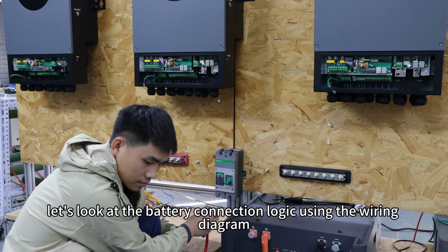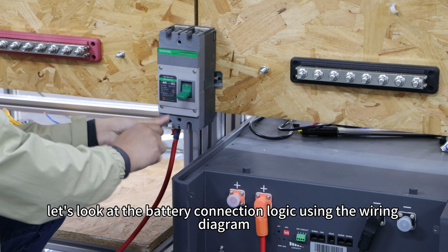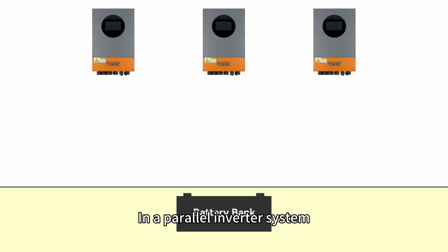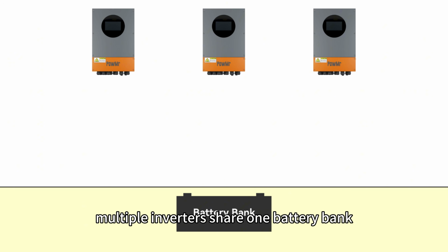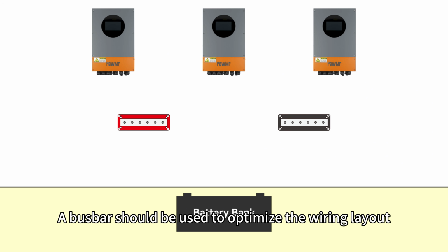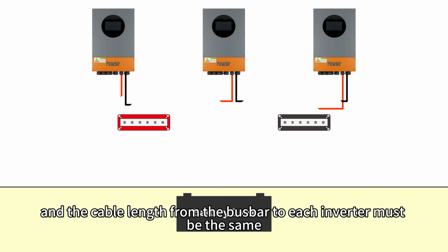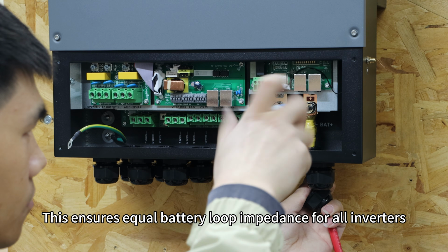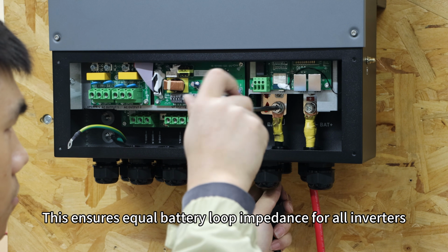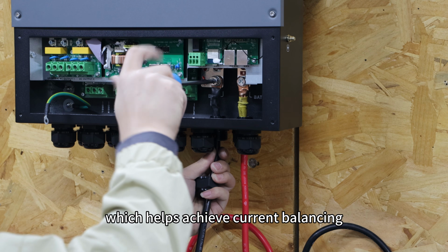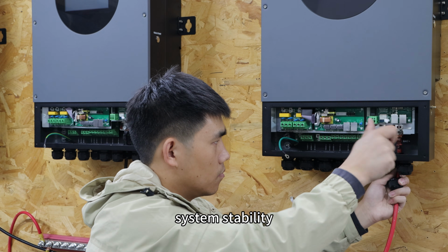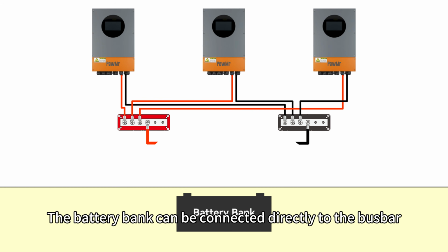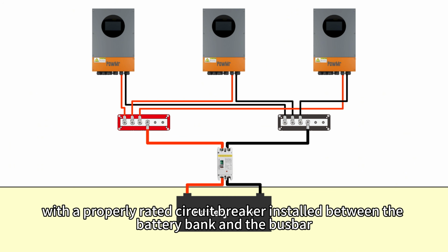First, let's look at the battery connection logic using the wiring diagram. In a parallel inverter system, multiple inverters share one battery bank. A bus bar should be used to optimize the wiring layout, and the cable lengths from the bus bar to each inverter must be the same. This ensures equal battery loop impedance for all inverters, which helps achieve current balancing, system stability, and equipment safety. The battery bank can be connected directly to the bus bar, with a properly rated circuit breaker installed between the battery bank and the bus bar.